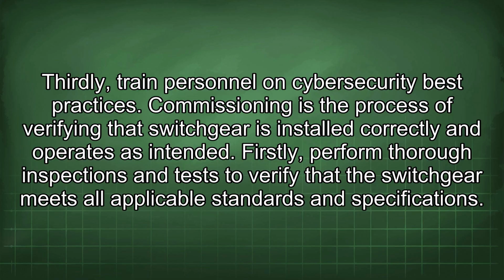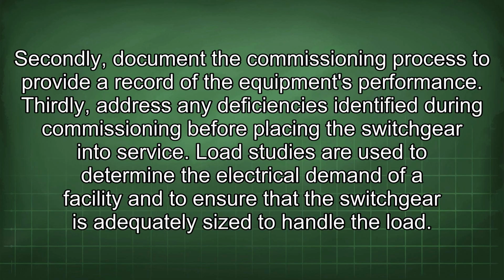Commissioning is the process of verifying that switchgear is installed correctly and operates as intended. Firstly, perform thorough inspections and tests to verify that the switchgear meets all applicable standards and specifications. Secondly, document the commissioning process to provide a record of the equipment's performance. Thirdly, address any deficiencies identified during commissioning before placing the switchgear into service.